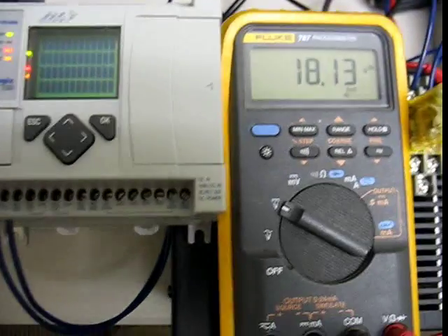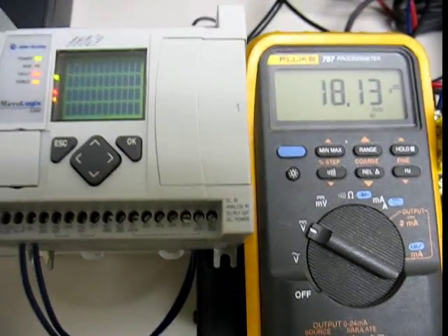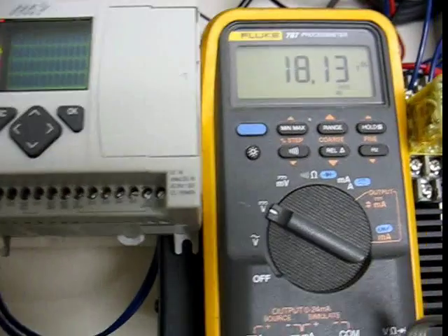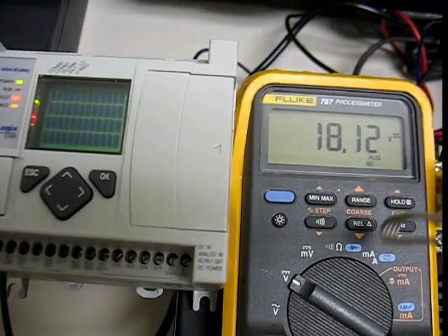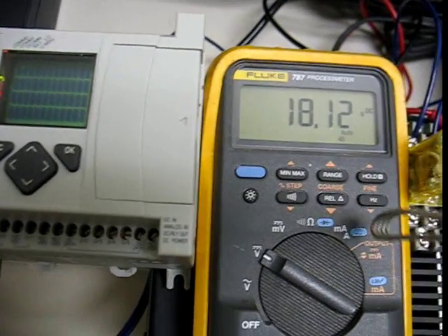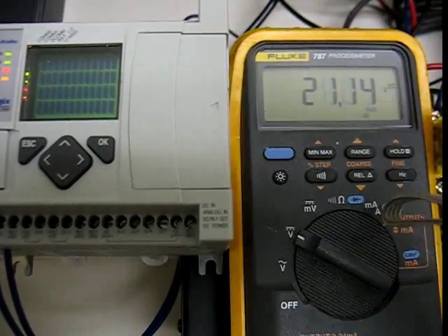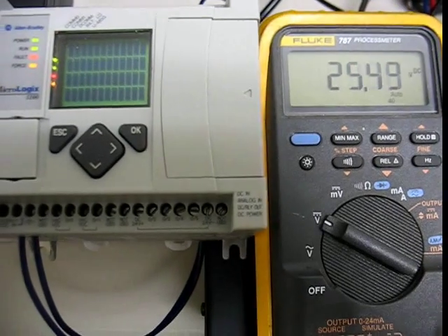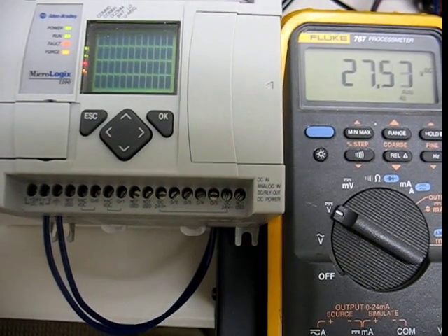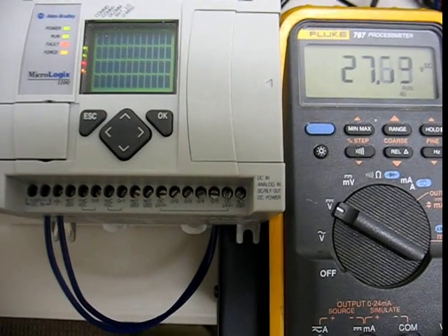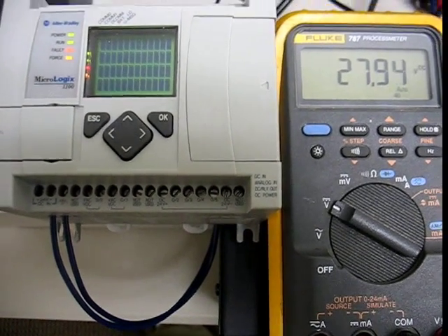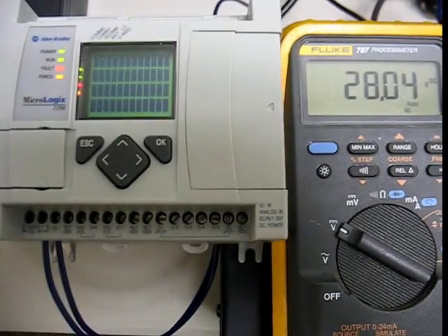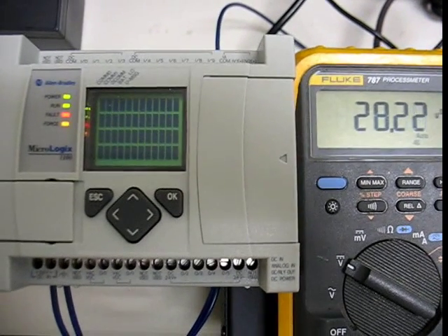So if I come over here now and hook up the battery charger to simulate a power restoration, you can see the battery voltage is going to come up and my processor doesn't restart. So at this point, you'd have to go out to the site and cycle power.